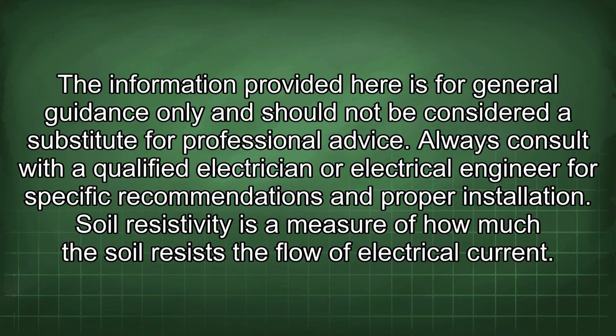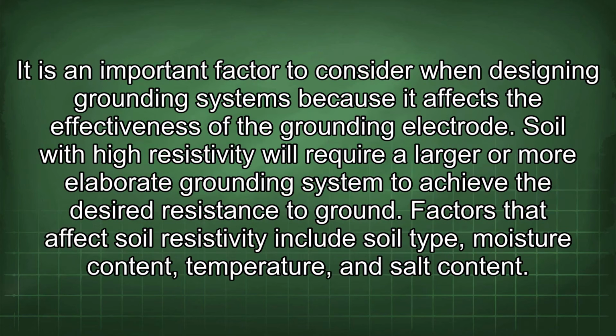Soil resistivity is a measure of how much the soil resists the flow of electrical current. It is an important factor to consider when designing grounding systems because it affects the effectiveness of the grounding electrode. Soil with high resistivity will require a larger or more elaborate grounding system to achieve the desired resistance to ground. Factors that affect soil resistivity include soil type, moisture content, temperature, and salt content.